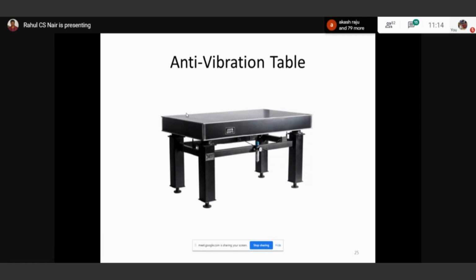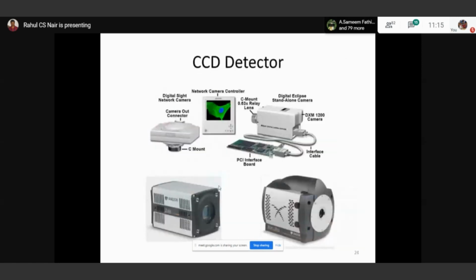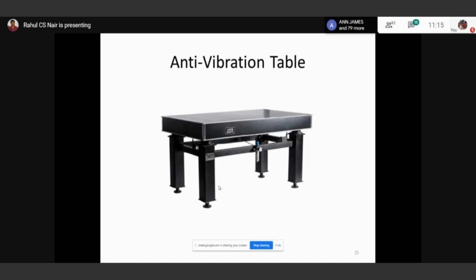All of this microscope setup needs to be placed in a vibration-free environment, right? So it should be placed on a specially fabricated anti-vibration table. You can see here it's a heavy platform, nearly weighing 110, and it is placed on bellows. Here you can see a pneumatic valve, and these bellows are inflated with suitable air pressure, so that if some disturbance occurs, it is automatically compensated by the mechanical level sensors fitted to these four legs. So it provides vibration-free functioning of the microscope. That is it for the fluorescent microscope.